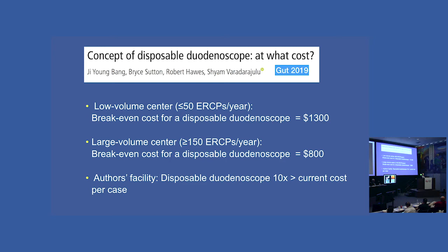So then you're probably thinking, okay, so if I'm going to switch to a disposable scope, that's got to be the price. Well, it's going to be higher than that. And by the way, the authors at the authors facility, they maintain that a disposable duodenoscope would cost 10 times more than the current cost per case. But if it's going to be higher than that, what you have to account for are all of the hidden real world costs. Because if you look at the amount of intensity required to clean these scopes, it's mind-boggling. When you look at the 150 steps that the personnel that clean these scopes have to go through with a minimum of 76 minutes, so over an hour per scope, with hands-on staff time for cleaning. And it requires extensive training and close supervision.